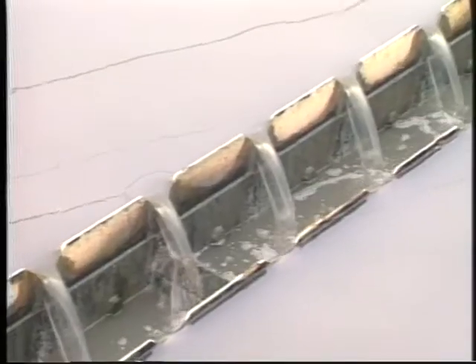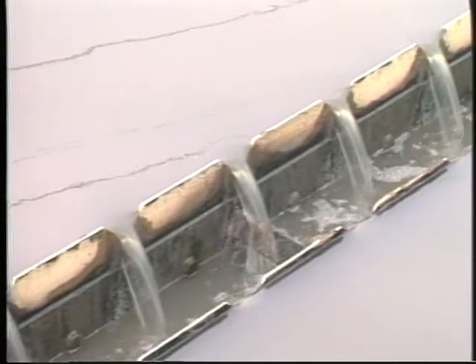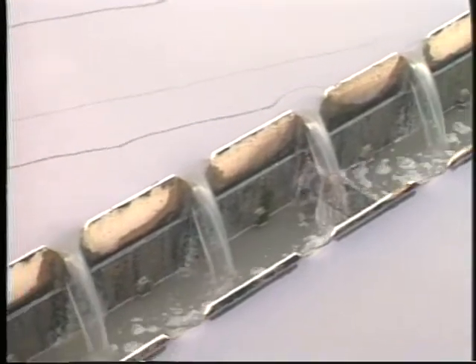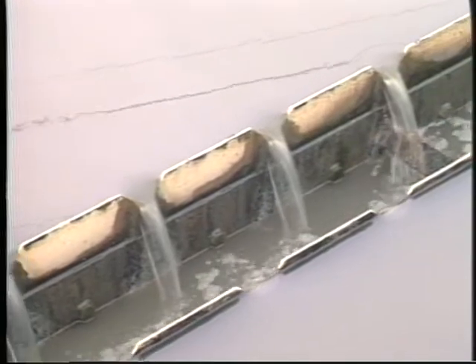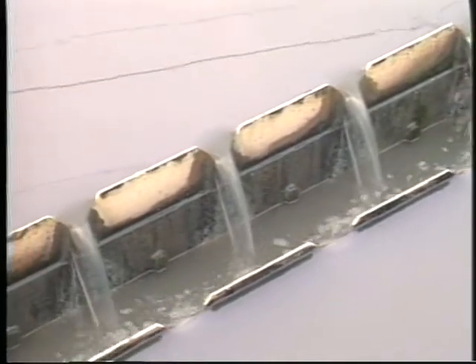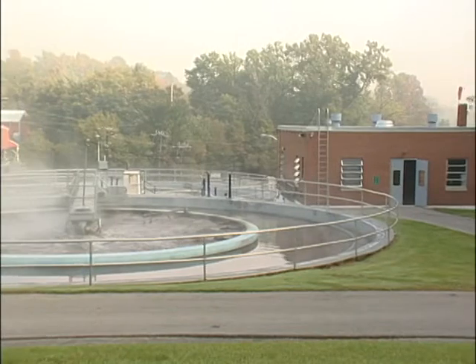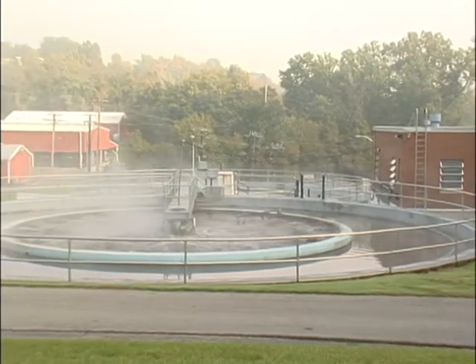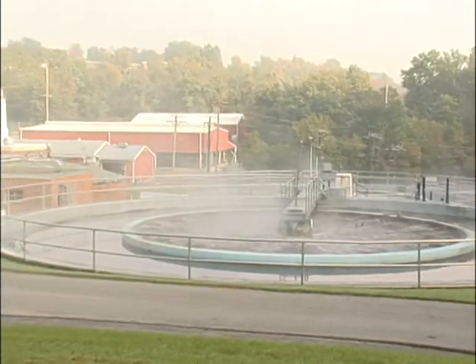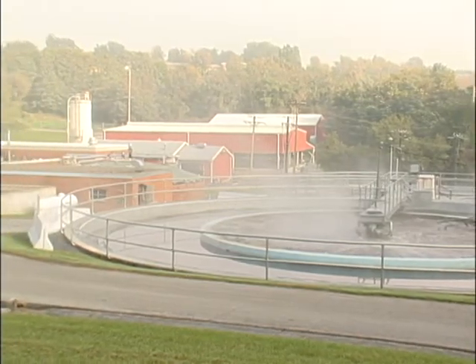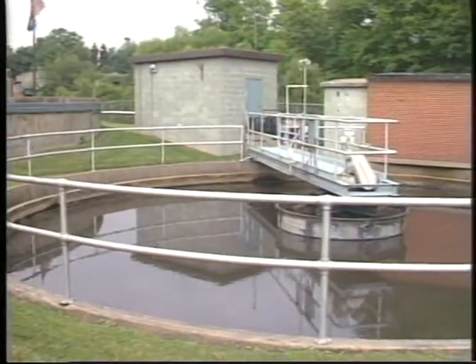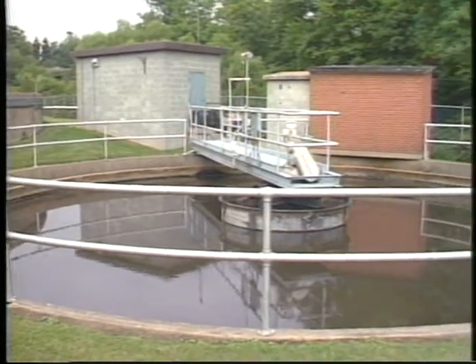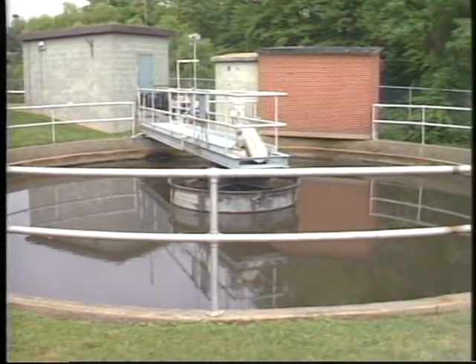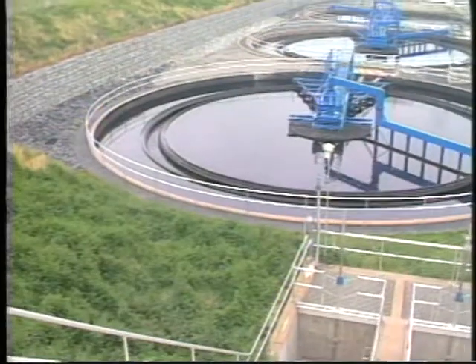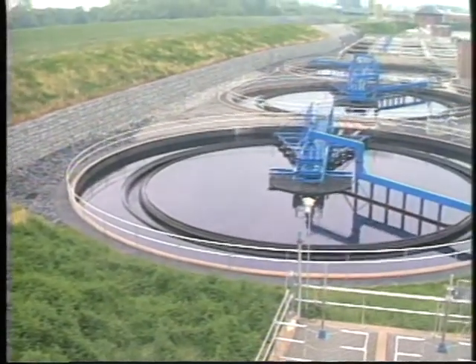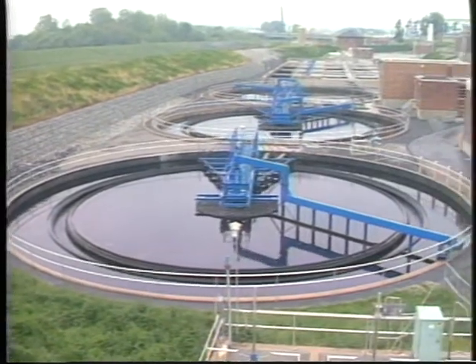It should be noted that primary clarifiers do not remove all solids. There are still colloidal and dissolved solids that must be removed by some type of secondary treatment unit. Secondary clarifiers are located downstream of a biological treatment stage. In advanced facilities that have more than one biological treatment stage, an intermediate clarifier separating the two biological treatment processes may be found as well. The clarifier following the final stage of biological treatment is usually known as the final clarifier.